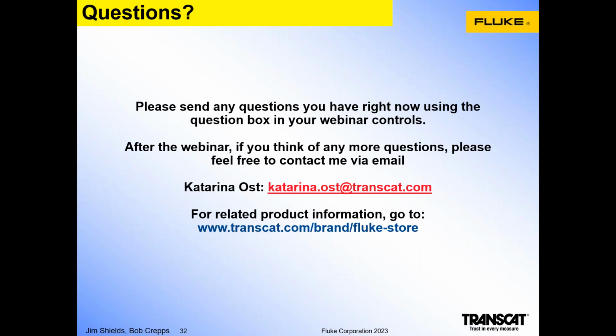Okay. What advice do you have for shops that are just starting to do calibrations and are using spreadsheets to record information? We have sample versions of this software that are free to use. And the nice thing about having spreadsheets, if you've got a spreadsheet by tag that has all the instruments in your plant, often those spreadsheets can be used to populate calibration management software. So if you have the inventory of critical tags in a spreadsheet in some way, shape, or form, there's a good chance you could import them into software to populate and create the tags without having to type all the information in.